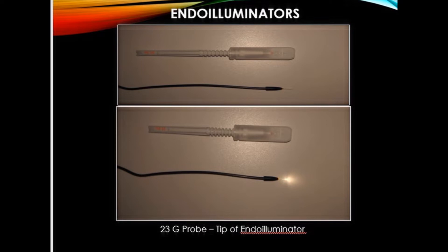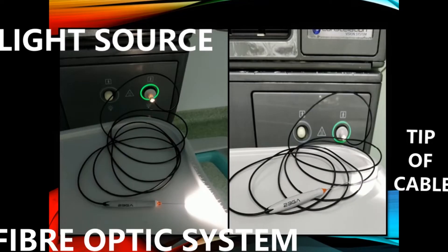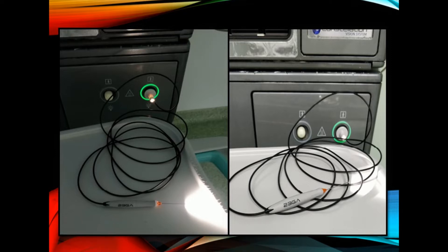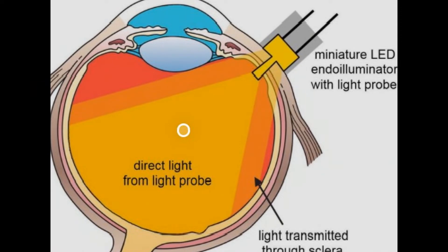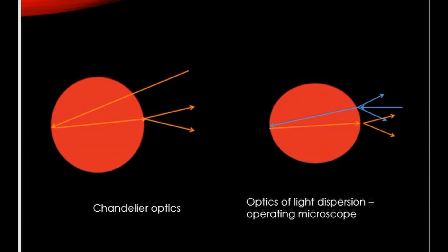The advent of endoillumination has brought about substantially improved visualization by providing a stable, stationary and diffuse form of illumination. In chandelier illumination, the light source is fixed posterior to the lens via the pars plana route. The light is directed at the fundus and gets reflected back to retroilluminate the lens. The retroillumination is affected only once while the light rays exit the eye, as opposed to microscope illumination wherein it is affected by the corneal opacity twice — during entry as well as exit.